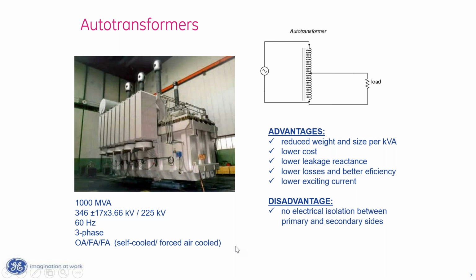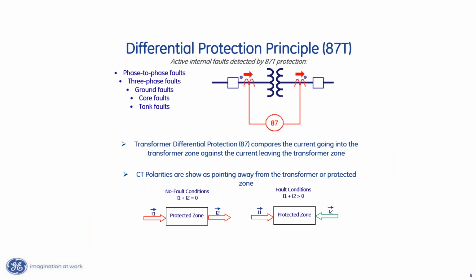Okay. So if we're going to talk about transformer differential, let's talk about what transformer differential is. Differential, basically, it doesn't matter if it's transformer differential, motor stator differential, generator stator differential, or even a bus differential, for that matter, a line differential. Differentials all work by the same principle. We're going to measure the current into the zone of protection, and we're going to measure the current out of the zone of protection. Those two currents should vectorially sum to zero. If they don't, we have a fault.